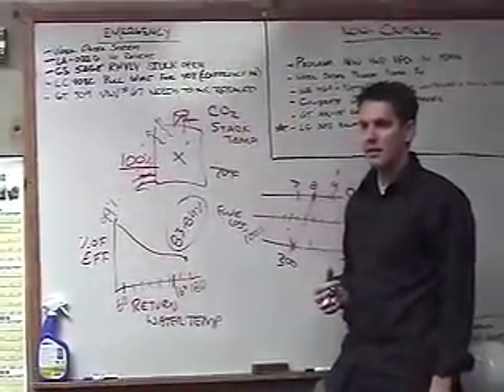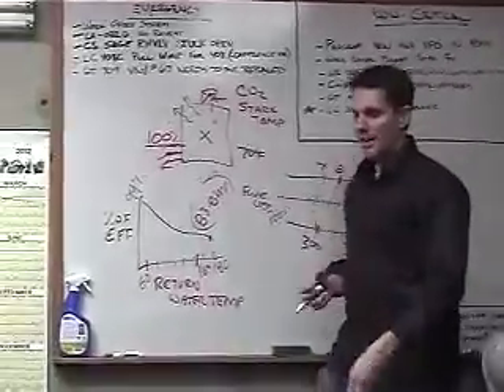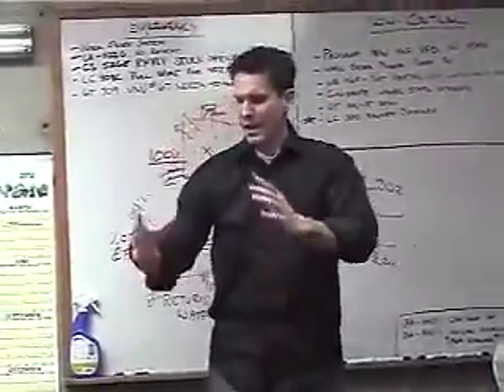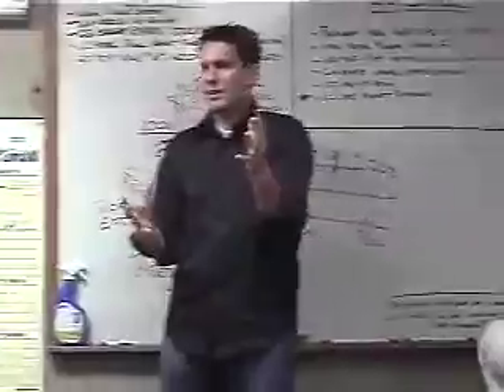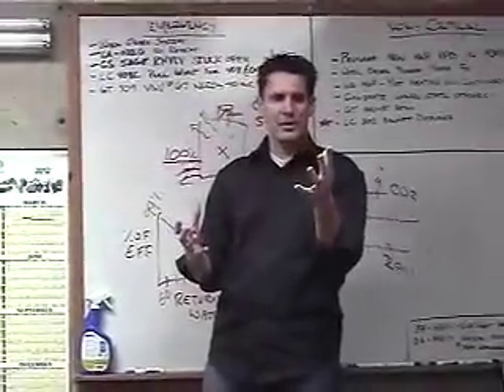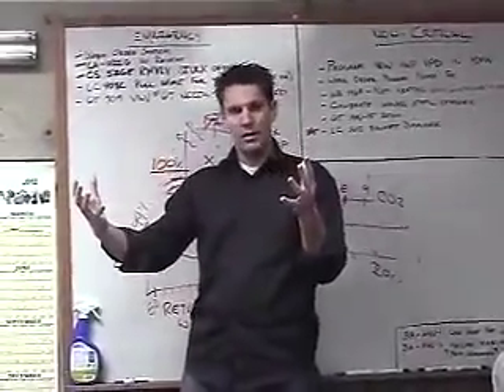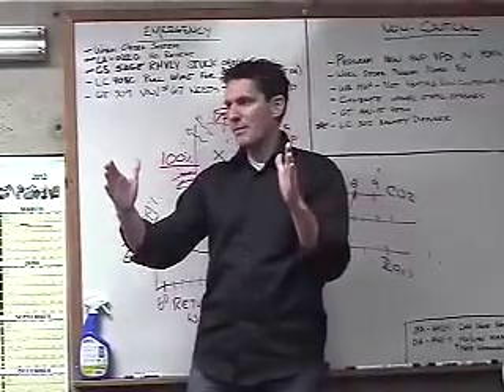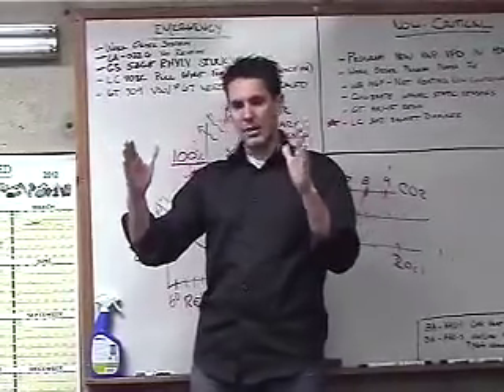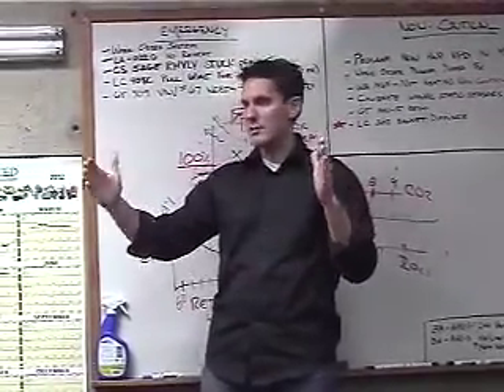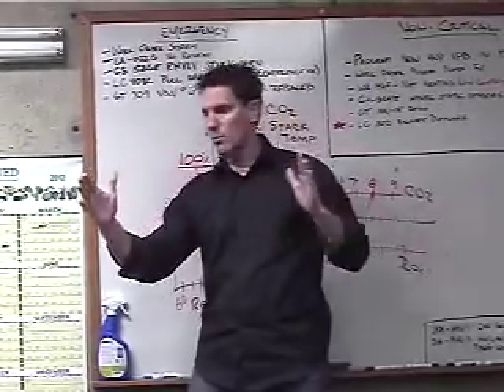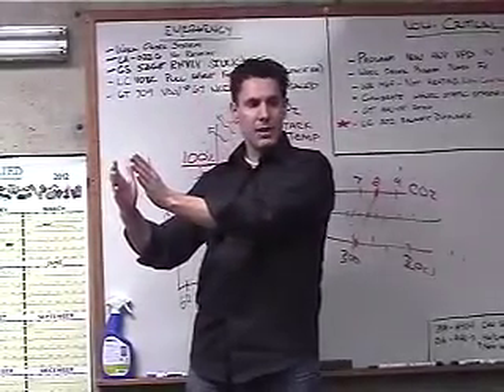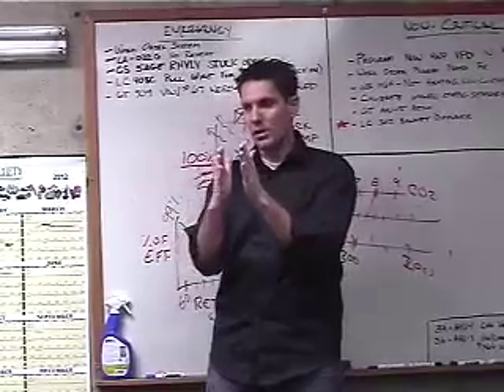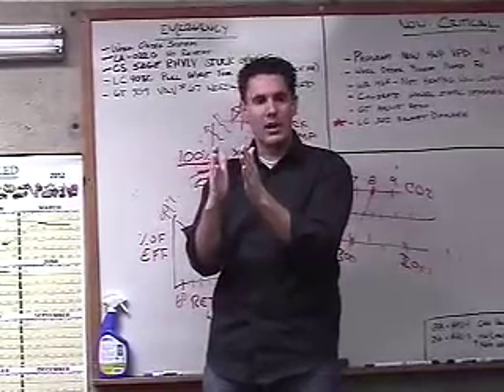More latent, it's absorbed out of the steam. Okay, there's more. Think about your hot flue gases. They start at around 3,000 degrees, and then you've got your water. With anything involving heat transfer, the greater the difference between my two mediums, the more heat will pass to the colder medium. If that gap shrinks, I don't transfer as much heat anymore.